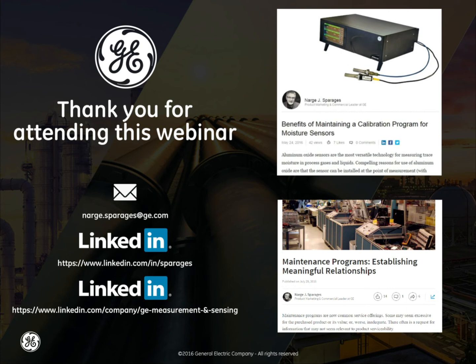I have another question here. In the presentation, you mentioned that there are various types of calibrations. What types are you referring to, and why would there not be one type? Calibration is intended to mimic, to some extent, the application the sensor is in. So if the sensor is always exposed to ultra-high purity gases, very, very dry gases, and it's there all the time, and then you have excursions to other alarm points or past alarm points that you're very concerned about, the calibration ought to mimic that as much as possible.